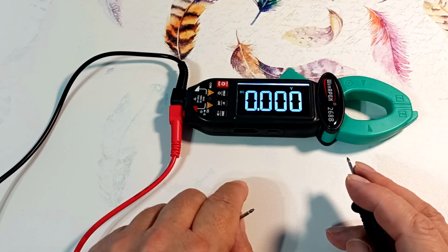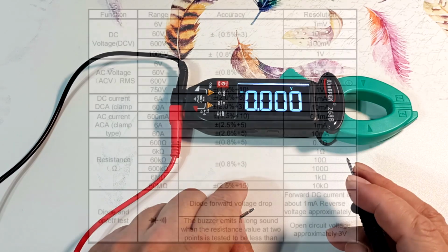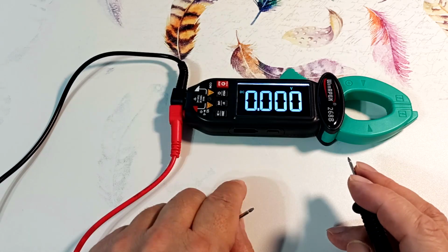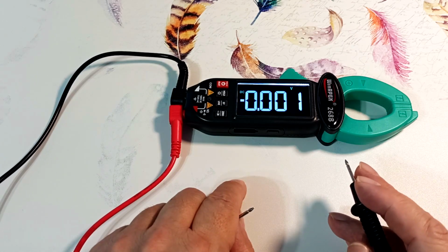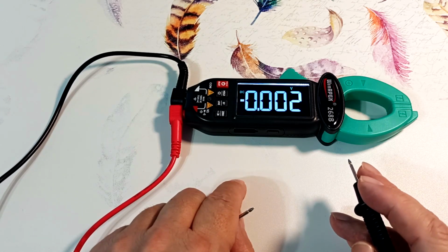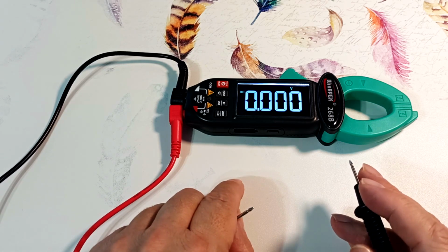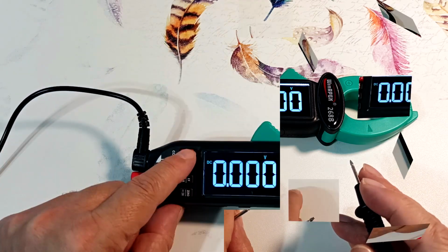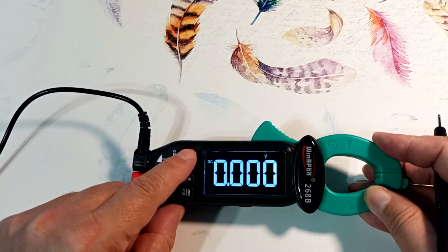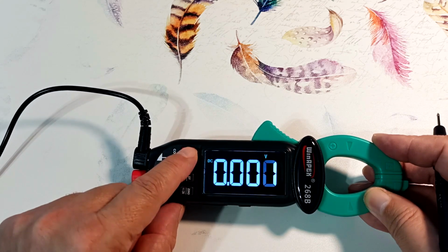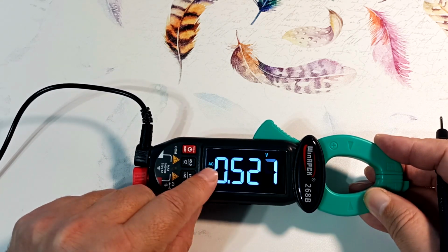The device selects the measurement range itself. The maximum voltage that it can measure is 1000 volt. When the voltage that the device can measure is exceeded, it displays the OL value. Input impedance of the device on all ranges, 10 mega ohms. Press the button again and go to the AC voltage measurement mode. The AC icon tells us this.